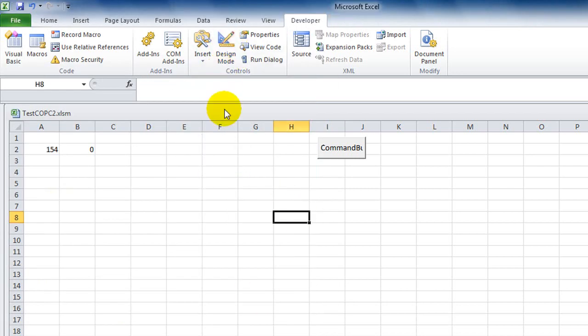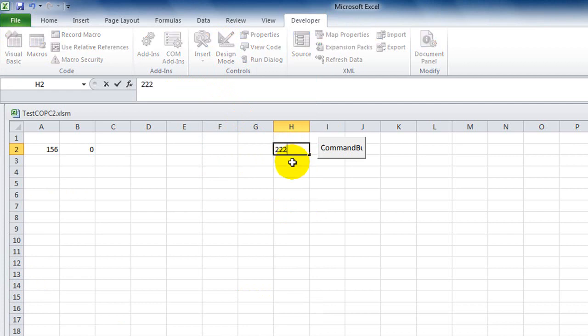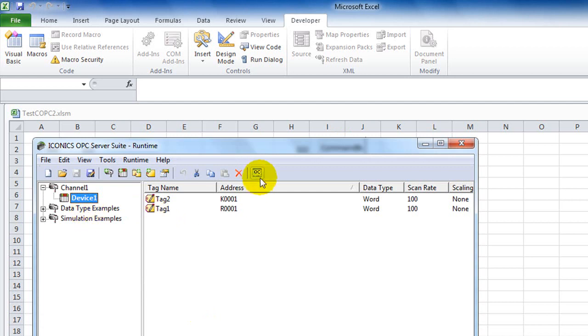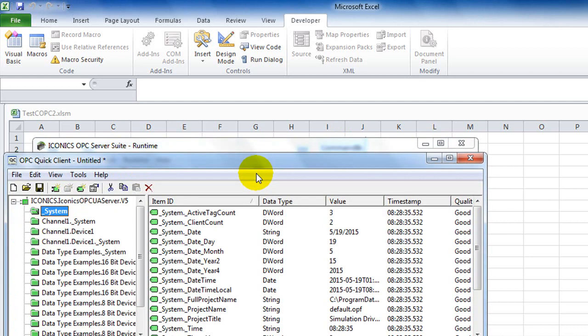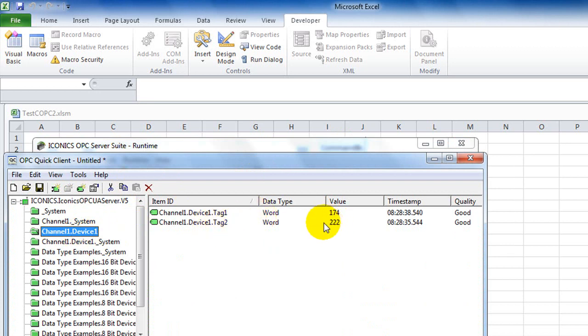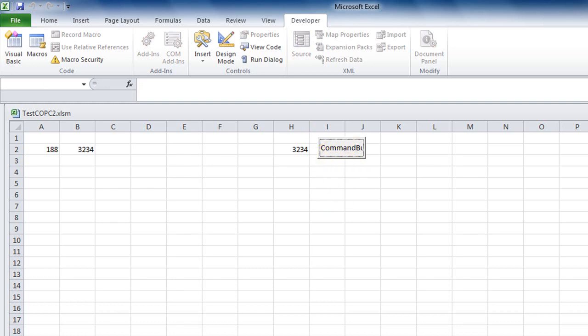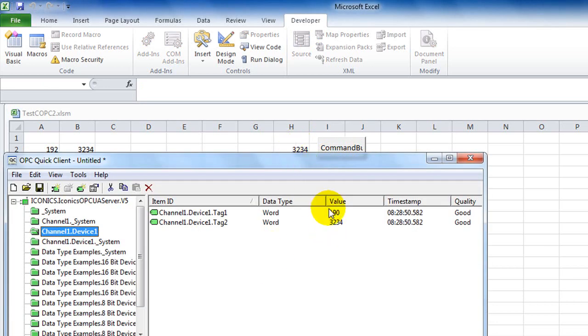Exit Design Mode, enter a value in the input box, and click the button. The value has changed. To verify, go to the OPC server and open Quick Client — on Device 1, Tag 2, the value is now 222. Back in Excel, enter a new value and click Write again. It changes corresponding to the value entered. This is the simple application to read and write OPC tags from an OPC server. Thank you for watching.